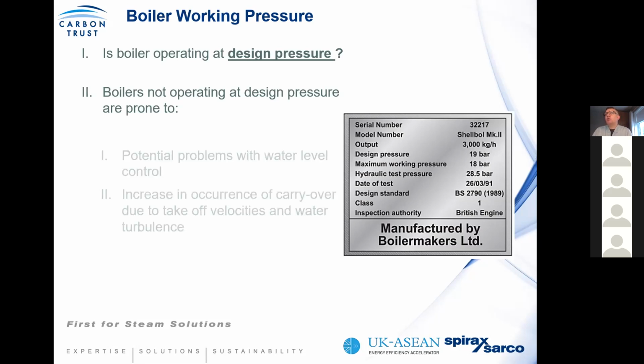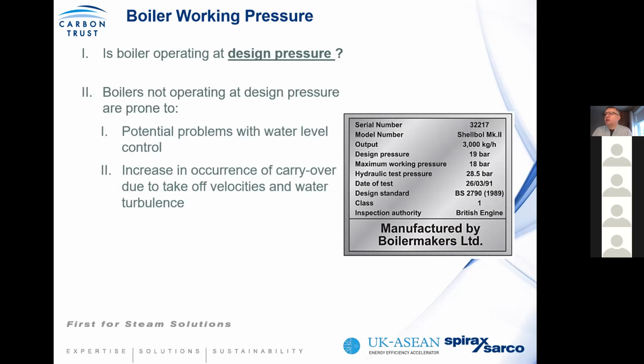Where it's operating below its design pressure, you could potentially have problems with water level control, because you get this swell effect, which is this movement in boiler water level depending on the loads and conditions. Also, where the boiler is below its design pressure, the more turbulent water surface, because of larger steam bubbles, means there's a greater likelihood of what we call carryover because of the velocities of water and the turbulence on the water surface. So in other words, it's better to operate the boiler to design pressure as we recommended in the fundamentals, and then reduce the pressure as required for distribution.